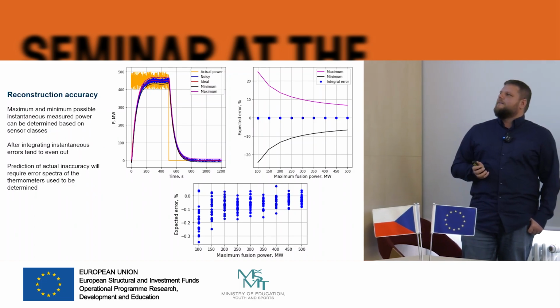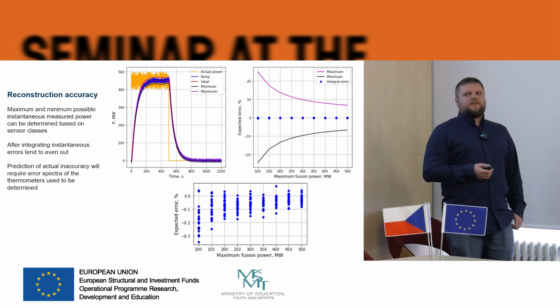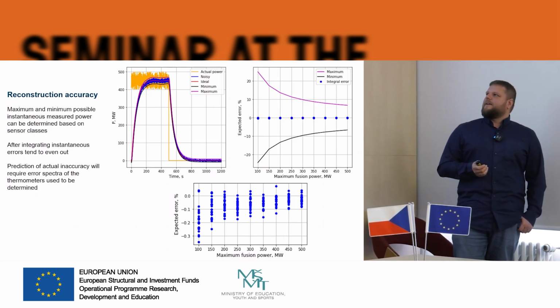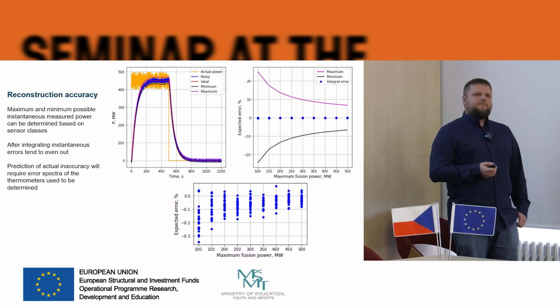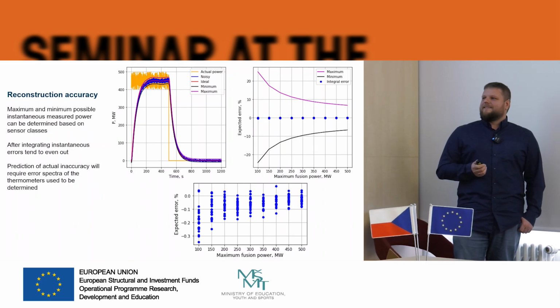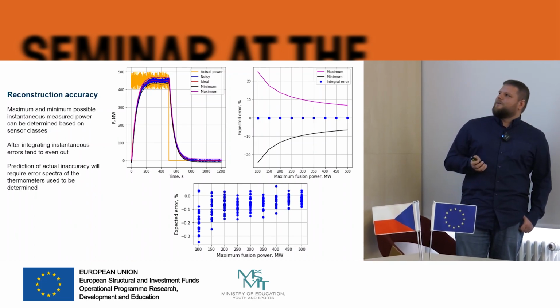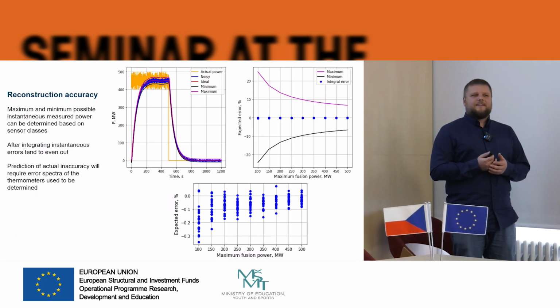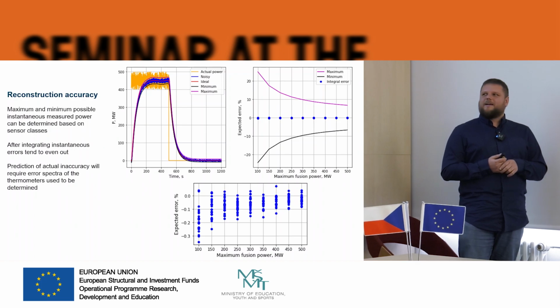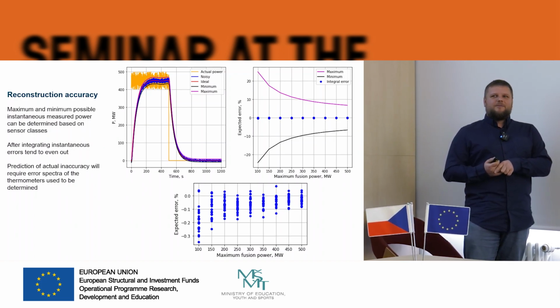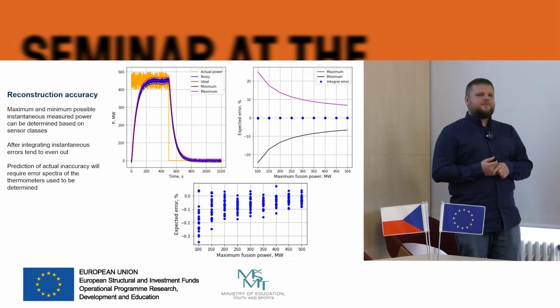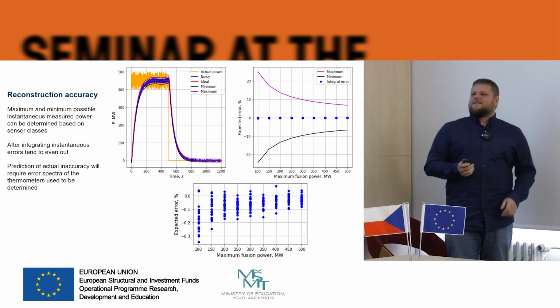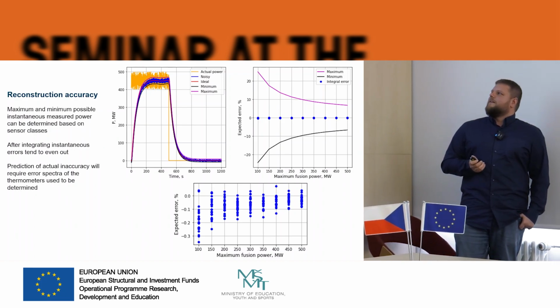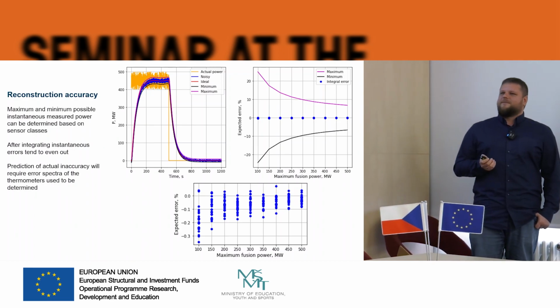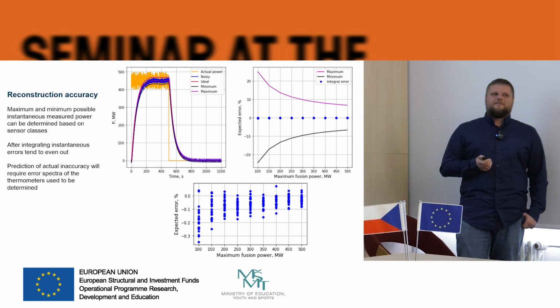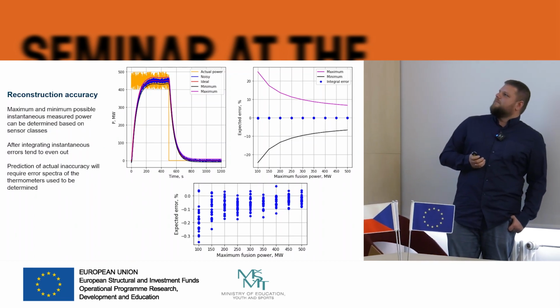This is quite relevant for the operation of the tokamak, because the regulator gives us the license to operate only up to 500 megawatts. They expect us to operate within the range of accuracy of the neutron system. So if we have a license to work at 500 megawatts, and the accuracy of the neutron system is 10%, we are supposed to operate at 450 megawatts just to be sure we never exceed 500 megawatts. If we improve it to 6%, for example, we can go further by 20 megawatts. That's already billions of dollars in the future operation of power plants, so it's very important from that point of view.